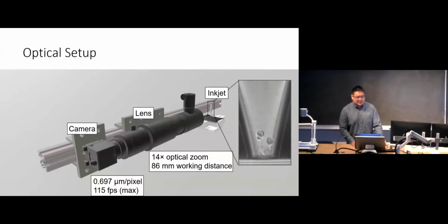Onto our instrument's hardware design. Here's the optical setup we use, where the imaging system consists of a camera and a zoom lens mounted in line with our nozzle, with the substrate moving below the printed area. The lens has a 14 times optical zoom and has a working distance of 86 millimeters, allowing the printer to accommodate substrates with footprints of up to a standard well plate. The camera and lens have a pixel resolution of 0.697 micrometers per pixel and a maximum frame rate of 115 frames per second. As shown here in the video on the right, the imaging system is capable of resolving cells passing through our nozzle.